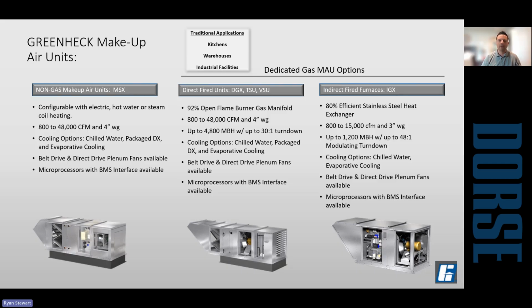One of the things that I'll caution against with the indirect fired is that the standard ones have like a 4-to-1 or 6-to-1 turn down. So your minimum temperature rise can be rather high because of that. When you start to factor in that during idle conditions, you could have a 50% reduction in airflow, and then you have that minimal turn down. In some cases, I've looked at these and you're turning on heat below 60 degrees and your minimum temperature rise is 25 or 30 degrees. So right away, you're overheating the kitchen. So just be careful if you're looking at the indirect product line.